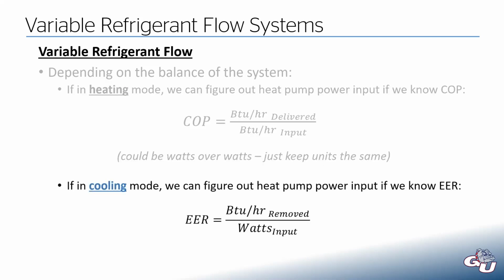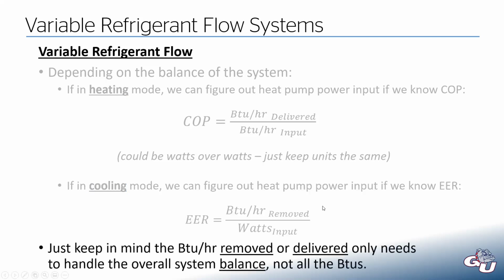But if we figure out, hey, our system is mostly in cooling mode, and if we know the EER, if we know the cooling efficiency, then we can figure out the watts input based on the known EER and the balance of the BTU per hour that we're taking out of the system. But just keep in mind that the BTU per hour removed or delivered, so the top terms in both of these equations, that's just the overall system balance. That's not all of the BTUs in the system. That's just the balance after we've shared energy internally.